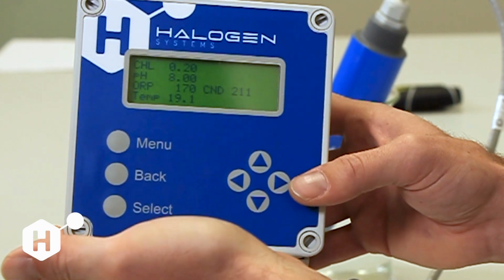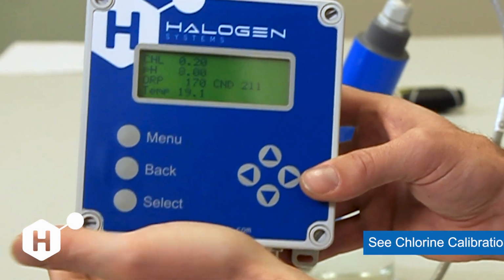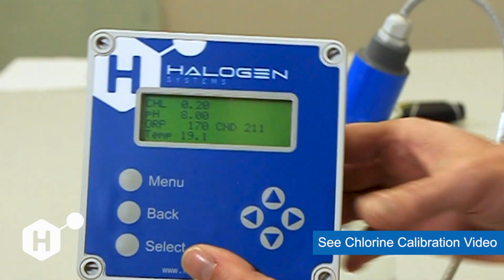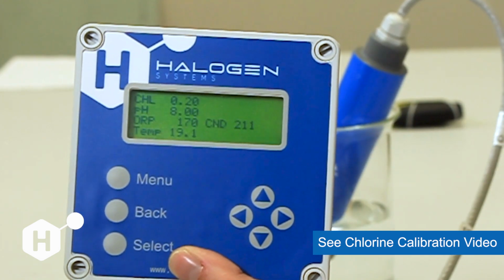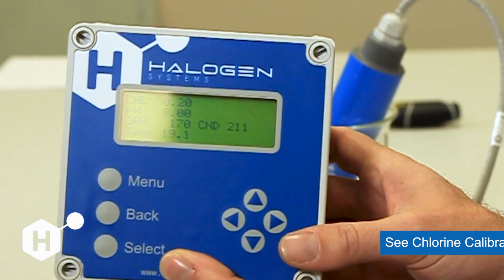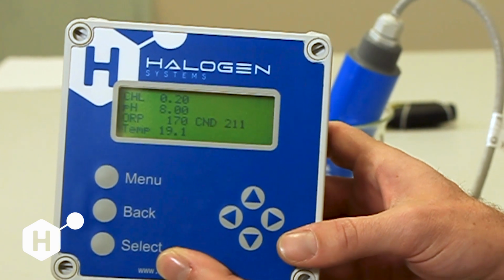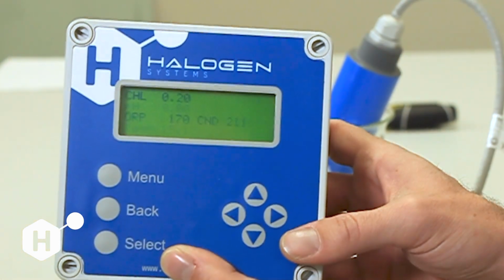Another good thing to do at this time is a quick accuracy check. You can do that using a pocket colorimeter to confirm that our chlorine measurement is matching the actual concentration within the solution that we're running in.